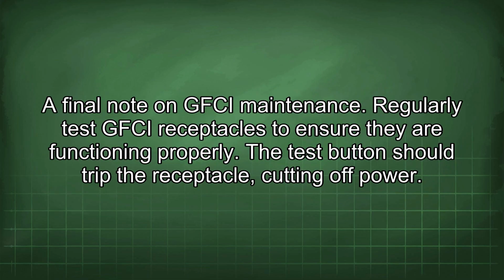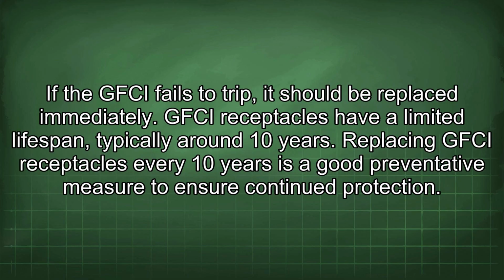A final note on GFCI maintenance. Regularly test GFCI receptacles to ensure they are functioning properly. The test button should trip the receptacle, cutting off power. If the GFCI fails to trip, it should be replaced immediately. GFCI receptacles have a limited lifespan, typically around 10 years. Replacing GFCI receptacles every 10 years is a good preventative measure to ensure continued protection.